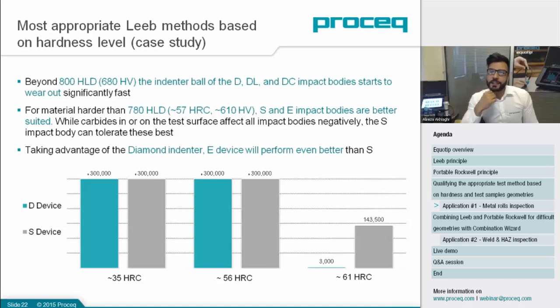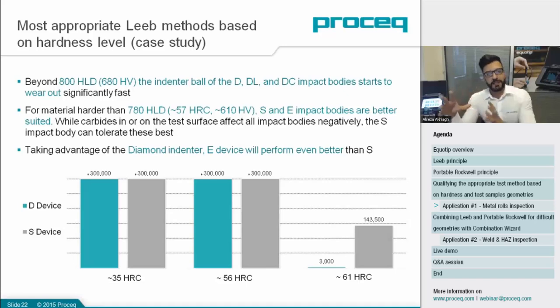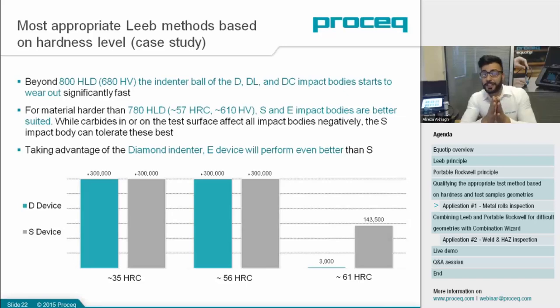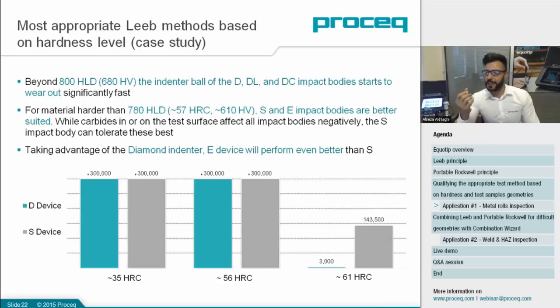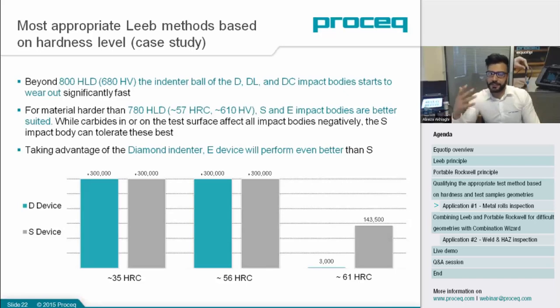Based on that, we can say the E-device would perform even better than the S-device given its diamond indenter. The E-device is the tool that should be utilized for such high hardness testing. However, there is a price premium due to the diamond indenter. But nothing stops you from using the S-device, which is not that far from the D-device in price, and it will give you the repeatability and reliability you expect. By understanding how each probe is made and its purpose, you'll be in a position to make the correct decision and qualify your instrument before starting the test.